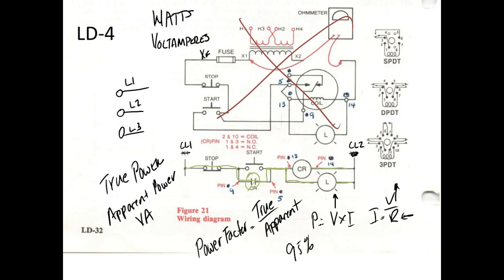They charge you a penalty, not us, not residential. Our power factor is corrected for us. But industries like US Steel monitor that power factor all the time. They had some big synchronous motors out there that they could overexcite and move the power factor around to where they wanted it. So US Steel actually had dynamic power factor correction. Alabama Power tries to do that if there are big substations. They'll have big capacitor banks that they dynamically switch around to try to get as close to 100% as they can.